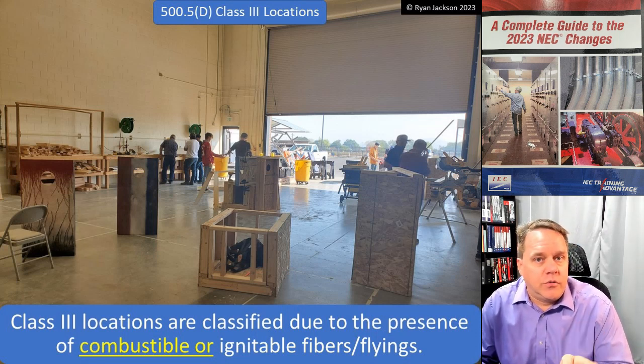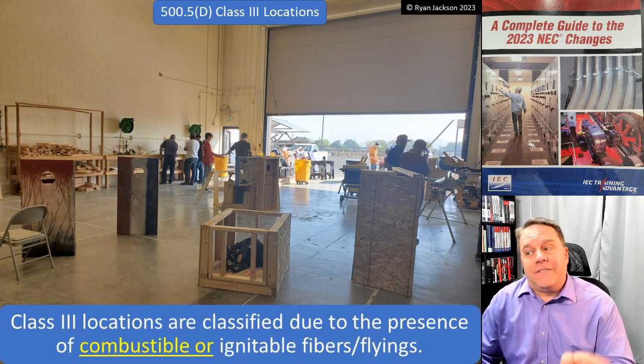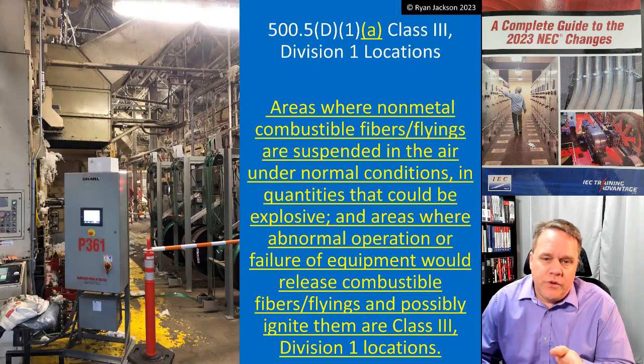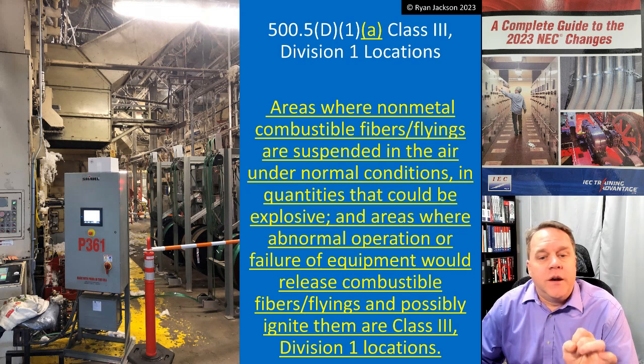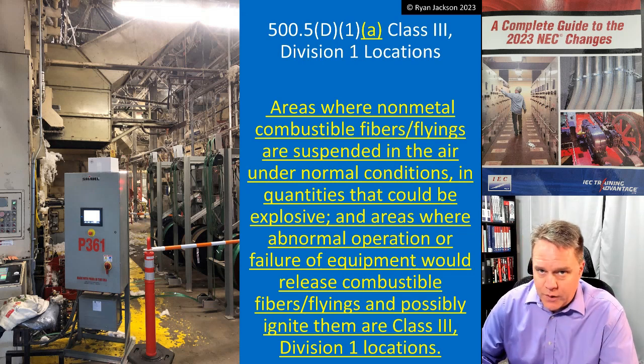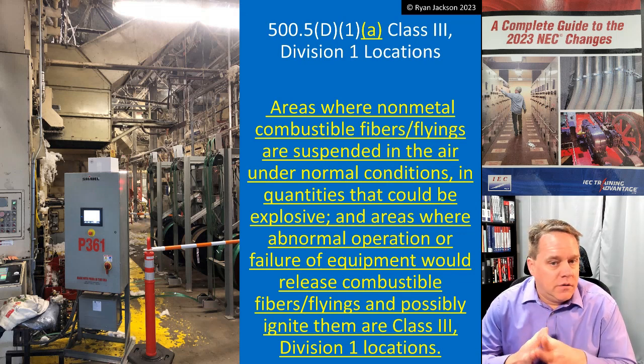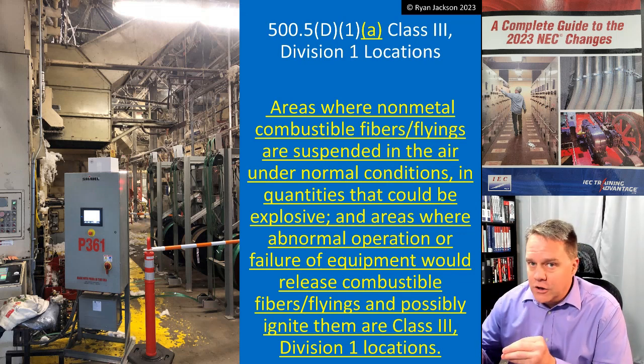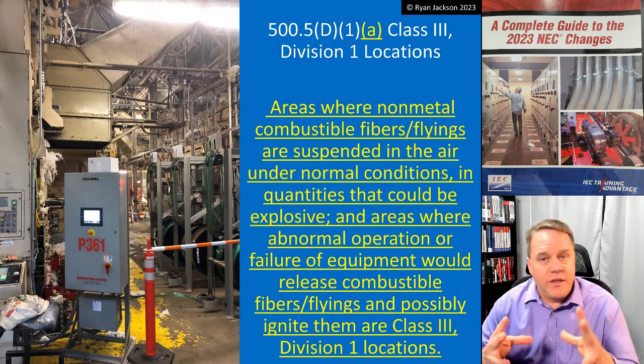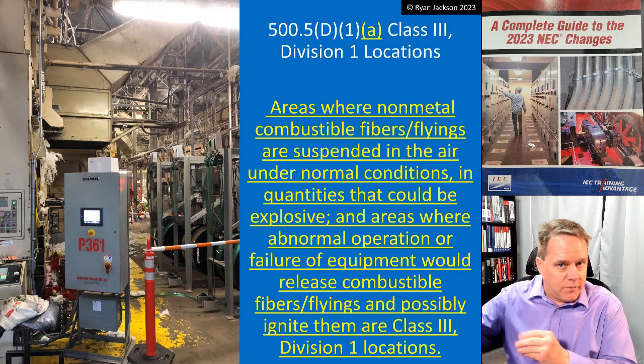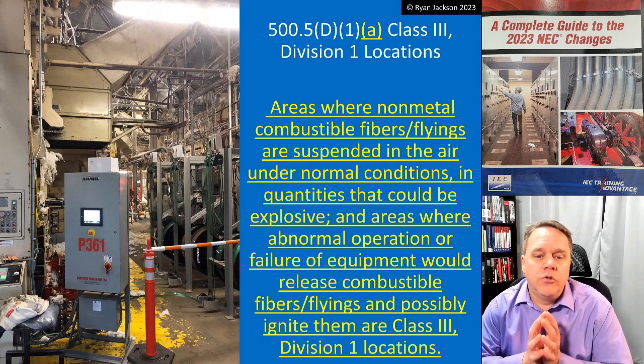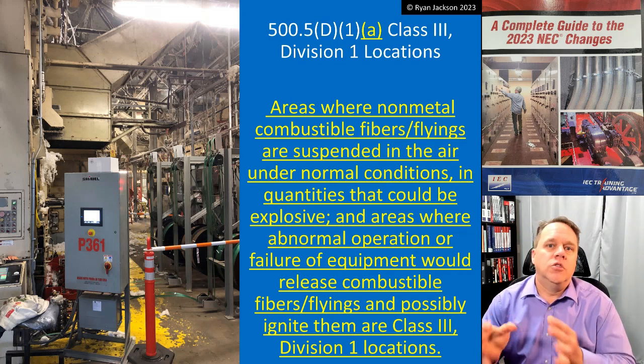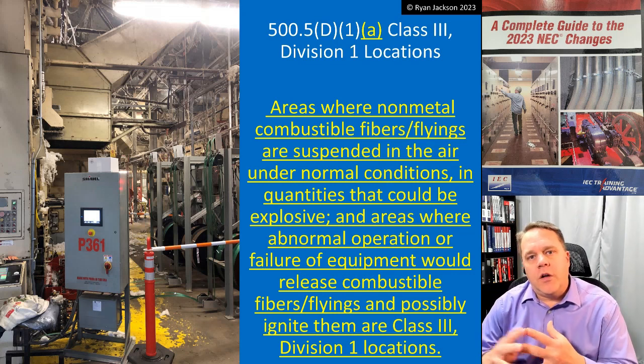When do you have a Class 3 Division 1 versus a Class 3 Division 2? It's still not perfect, but it's definitely better than it has been. Class 3 Division 1 locations per 500.5(D)(1)(a) are areas where non-metal combustible fibers or flyings are suspended in the air under normal conditions. The key point is non-metal fibers and flyings — if you're dealing with metal materials like aluminum or zirconium, that's a different classification entirely.